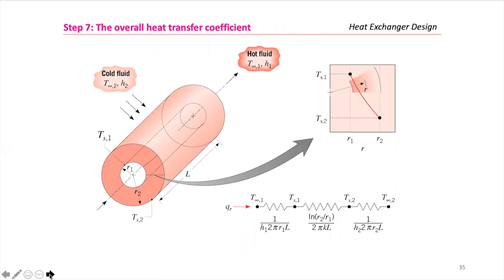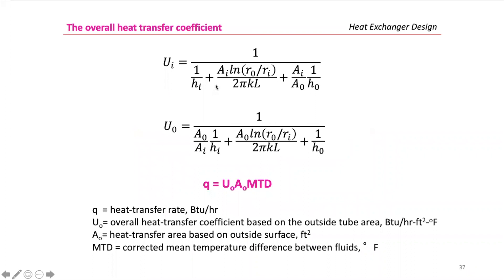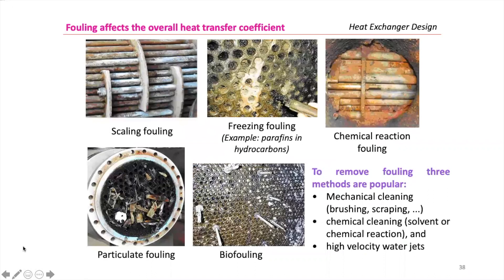The next step is to calculate the overall heat transfer coefficient — the sum of all resistances — which we have practiced with the LMTD method using the electrical analogy: convective plus conductive plus second convective. Sometimes we need to add fouling effects, because of the use we give to our heat exchangers. Different types of fouling include scaling, freezing fouling (common in paraffins and hydrocarbon services), chemical reaction fouling, particulate fouling, and biofouling.